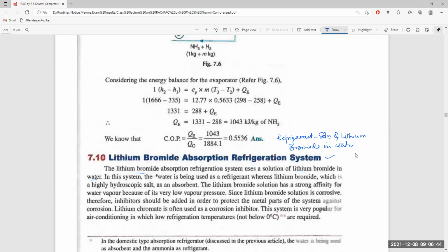water is being used as a refrigerant, whereas lithium bromide, which is a highly hygroscopic salt, is used as absorbent. So initially it was like this. Water was absorbent, and ammonia refrigerant. Here water is refrigerant, lithium bromide is absorbent. Just opposite. It is a strong solution, has a very strong affinity for water vapor because of its very low water vapor pressure.